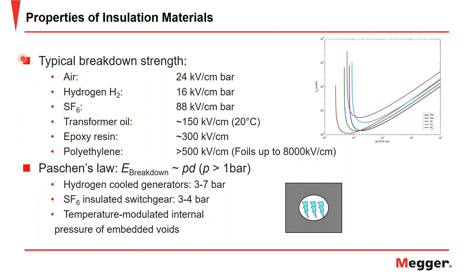And these gases, or this medium, as I mentioned when we were talking initially about the different insulating materials, cause different characteristics of PD activity. So the rise time in nitrogen, which is an electropositive gas, is much slower than that of SF6 or C5PFK, which results in a more narrow measuring bandwidth, whereas SF6, which is an electronegative gas, would have a larger bandwidth. And here we have Paschen's law, which directly relates the breakdown voltage to pressure times distance. Here we have an example of multiple different Paschen curves where on the y-axis we have breakdown voltage, and on the x-axis we have pressure times distance. And you can see how the voltage varies based on the pressure times the distance.